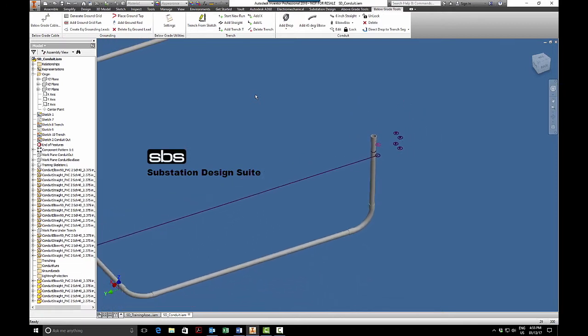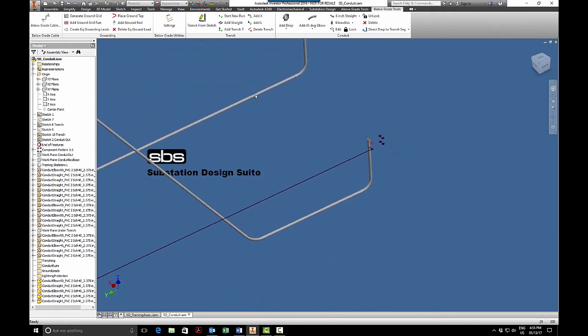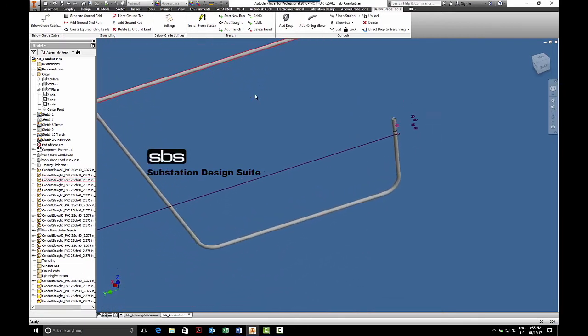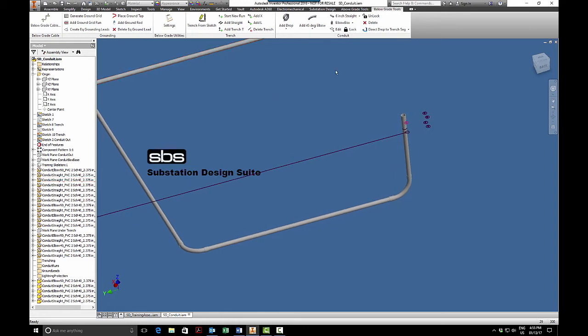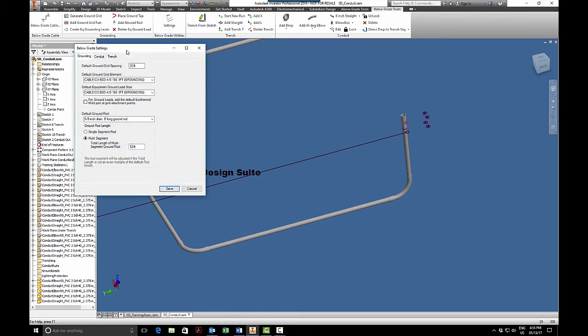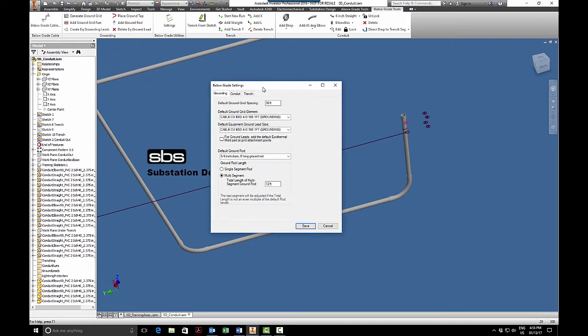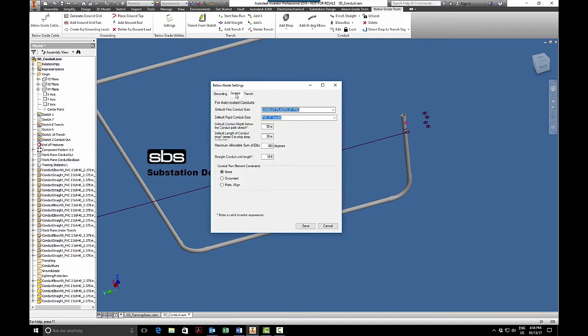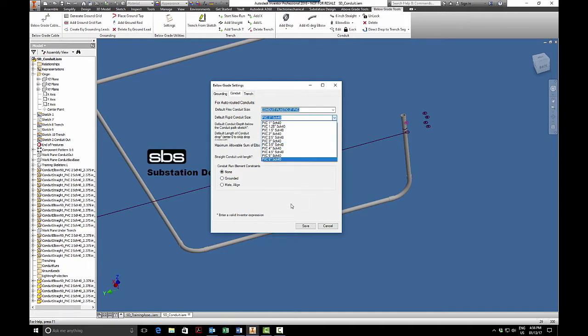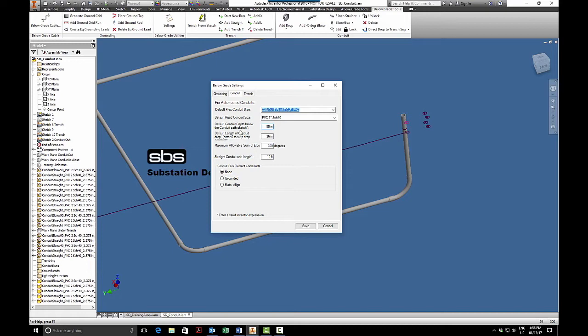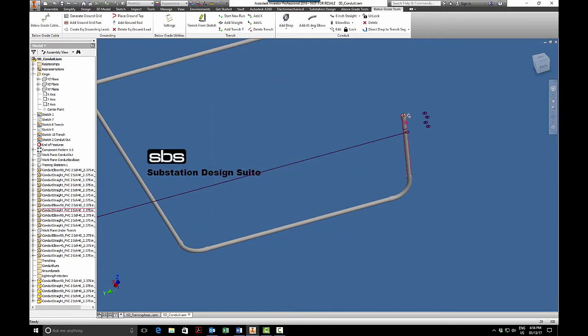Let's run some conduit. Let's first go to our settings, we'll check our settings, go to the conduit tab, and we're going to select three inch conduit. This is all editable in the Substation Design content editor. I'm going to leave it at three inches, I'm going to leave it at 50 inches below the depth of my sketch. So as I said before, my depth of my sketch is identified as top of concrete, so I'm going to go 50 inches below the top of concrete. I'll take the defaults, I always like it grounded, and I'll hit save.